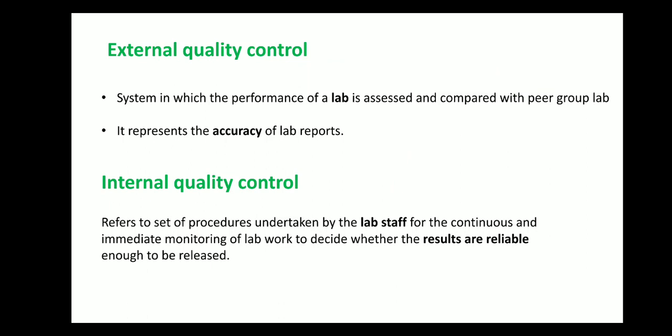There is also internal quality control. Internal means day to day; every day we run the QC. External we do once a month, and it is sent to a different lab, and after sending we get the result. Internal we have to run every day, and these values stay with us. We can analyze every day whether our instrument is working properly and whether there is any problem with the analyzer. So all this we can analyze.